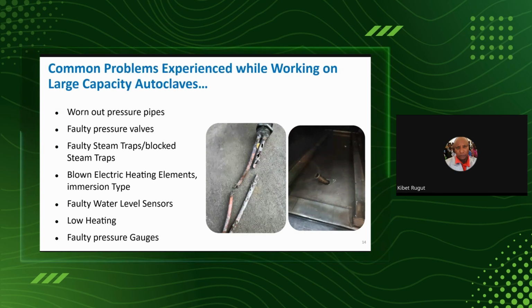Steam traps, maybe you get a lot of linen being blown when you are releasing the steam, or when you are releasing the water which is trapped. There's linen which gets trapped in the steam traps and causes leakage of those strainers. And electric heating elements, sometimes one may break if they are three-phase, and the other two may operate. So you find that the one which has broken is causing some electrical leakages. So it is also good during your inspection to look at the electrical elements.